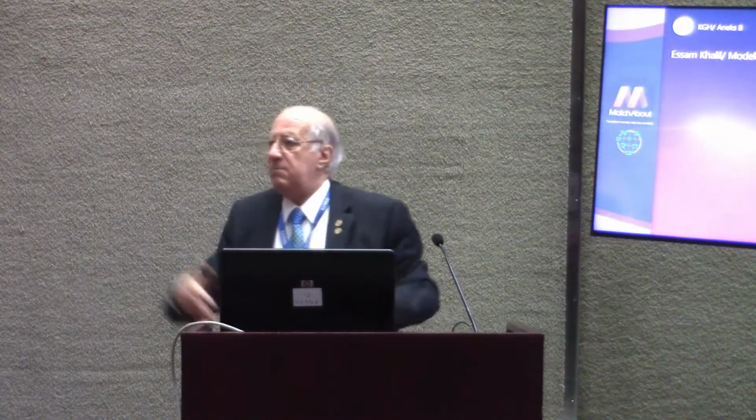as well as the pollutants. Normally we use three-dimensional computer software, typically with a grid size of about 8 million grid nodes on a PC. When I was doing my PhD at Imperial College, the maximum we could reach with my colleague Sraguddin was 8,000 points, 20 by 20 by 20. After that, the computer would say, sorry, bye-bye. Nowadays, on a laptop, you can sometimes reach 20 million grid nodes. And this procedure is iterative, so it's complicated. But we still use a lot of turbulence models to be able to account for the different activities.